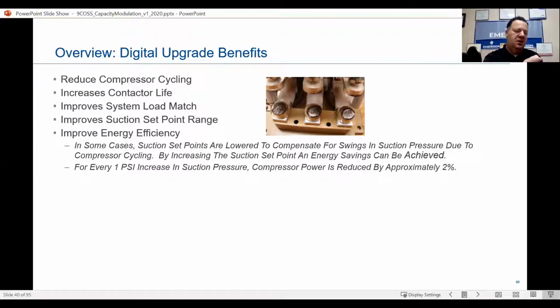Instead of slamming that whole RPMs on, or that whole BTUs or horsepower is coming out at the same time, will increase our contact life. You can see this visual here. See how that's all pitted up. Improves system load matching, as I mentioned. Improves suction set point range, and improves energy efficiency.